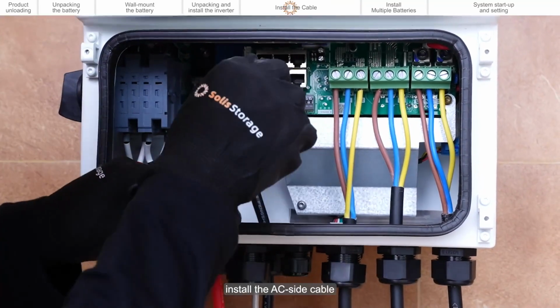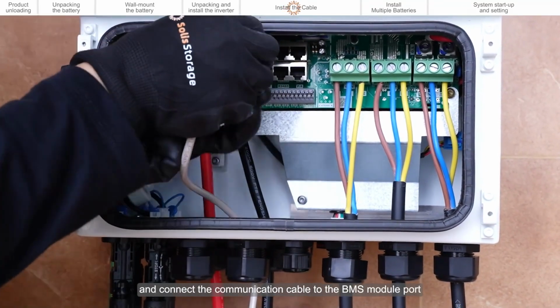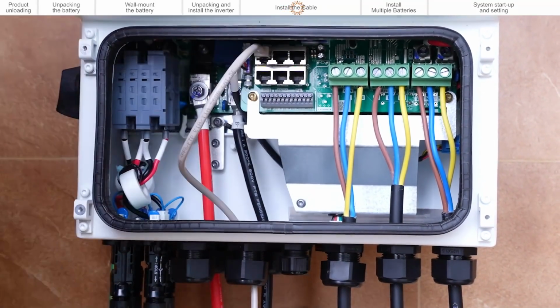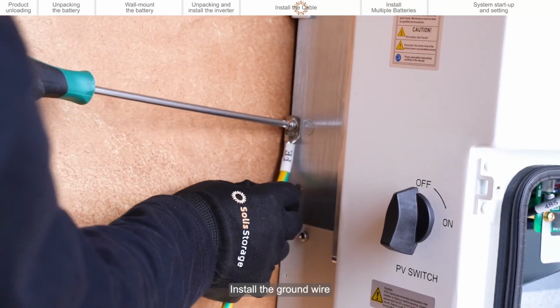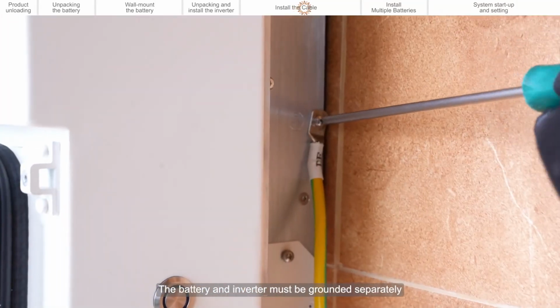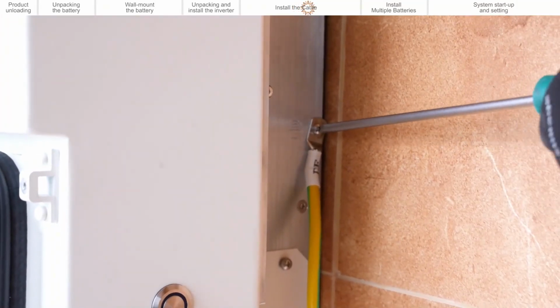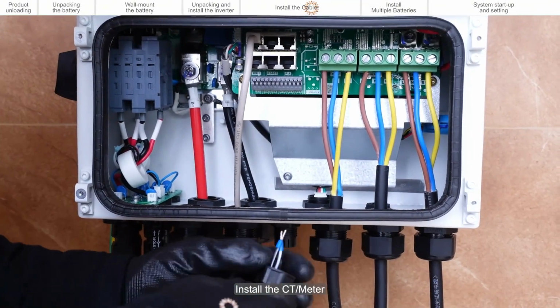Install the AC side cable and connect the communication cable to the BMS module port. Install the ground wire. The battery and inverter must be grounded separately. Install the CT/Meter.